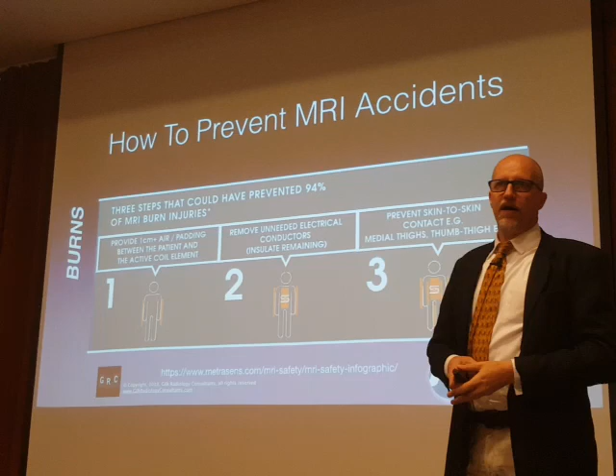The third most frequent source of burns is skin-to-skin contact. These typically manifest in large caliber body loops. So if we were doing a T-spine study, for example, and I was laying in the bore and my thumb was touching exposed skin on my thigh, we've created a large loop. We'll talk a little bit about this when we get to the physics portion of radio frequency, but when we transmit radio frequency energies into the patient, it induces currents in the patient's own tissues. Not enough that we're shocking the patient. That's time varying gradients, and that's direct neuromuscular stimulation. We'll talk about that as well. But the radio frequency transmission induces electrical currents in the patient's tissue. They're benign. They don't hurt. The patient is completely unaware of them.